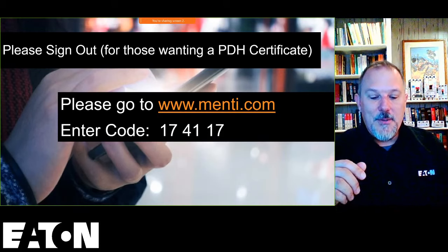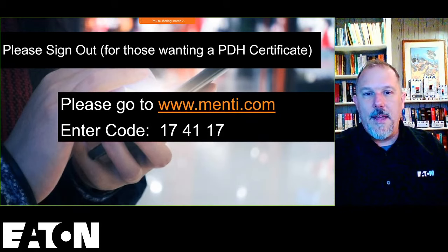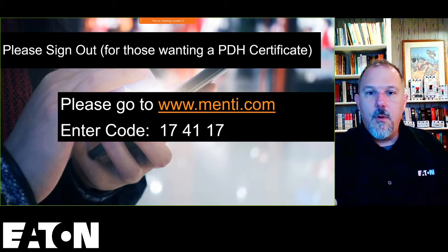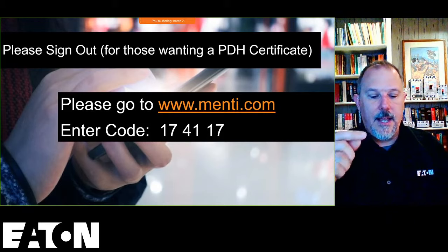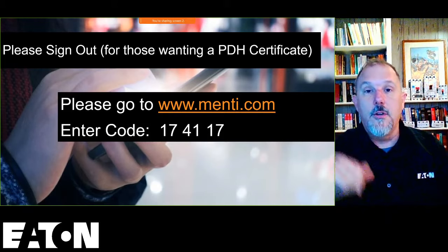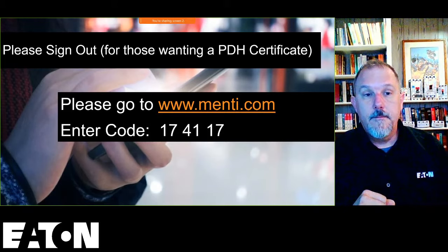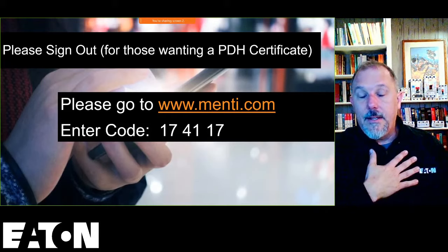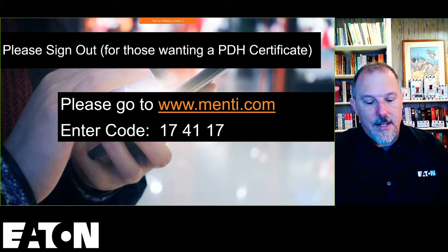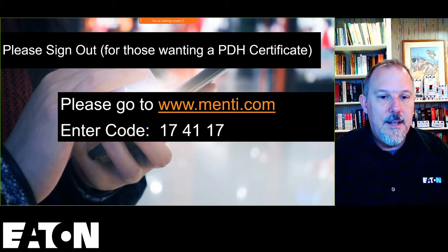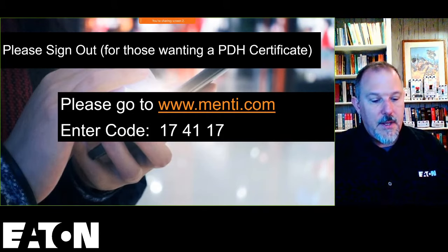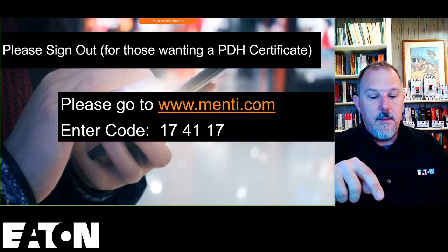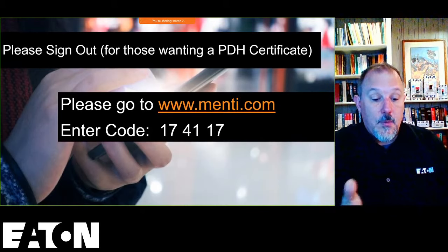Okay. So I can't look at the label on that AC unit, and it's not going to say this is a multimotor combination load equipment. I just got this label because I asked Donnie for a label because I couldn't find one that was good. But in any case, 440.35 makes it really clear that's what I do.